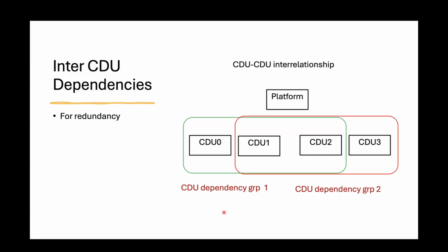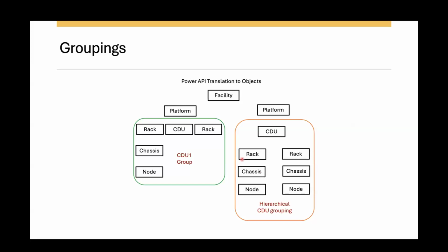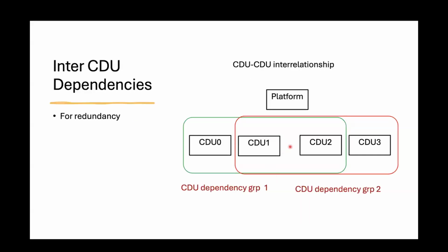And it's really useful to know, do you really need to shut down all the equipment that's sitting underneath here if we have a CDU failure, or can we absorb that into the rest of our system as a whole? So the idea here is that we can group not only objects like we had here with CDUs. Hey, here's a CDU and here's all the stuff it possibly can cool or is cooling, right? We can also use the same functionality to group CDUs with information about that group to tell us what that is. Now you might say, how do I end up with a group?